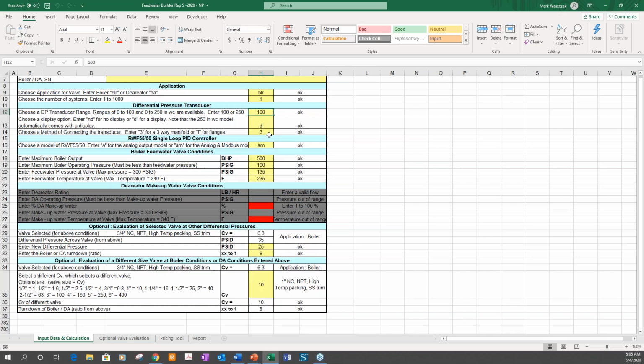What type of connection to the transducer? We chose three-way manifold. It's very nice because it allows you to isolate the DP transducer from the boiler without having to shut the boiler down. Whether you want Modbus or no Modbus, in our case we want Modbus. Next, you input what size is the boiler or the output, in this case 500 horsepower. What is the maximum operating pressure? In our example, we're going to use 100 psi. And what is the feed water pressure of the valve? We're going to use 135 psi. And finally, the temperature of 235.